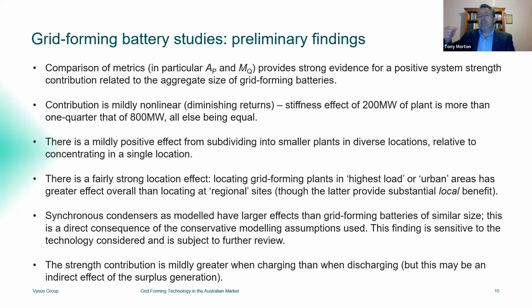We also did a very quick comparison with fairly generic synchronous condensers, and we do see a similar contribution, although the synchronous condensers were still making a greater contribution in our studies because we actually assumed that. So we took a conservative approach, and we deliberately wanted to bias things in favour of the synchronous condensers, just so we weren't drawing too optimistic conclusions for grid forming plants that are still an evolving technology. But what we do see is that they're still making a very impressive contribution to system strength compared with synchronous condensers, even where those synchronous condensers are optimized to the extent that we know we can do them now based on 100 years of experience. And we don't make those same assumptions about optimizing the grid forming converters. We still see that contribution being made.